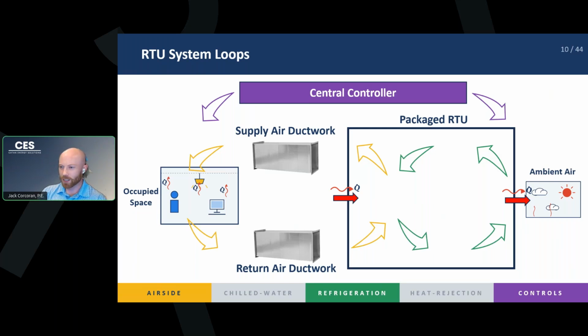The occupied space is generating our heat, right? And we're going to have to remove that heat from the air side loop into the refrigeration loop and then into the ambient air, right? And so we're not changing anything fundamentally here. It's just a matter of where each component fits in the configuration of the system.